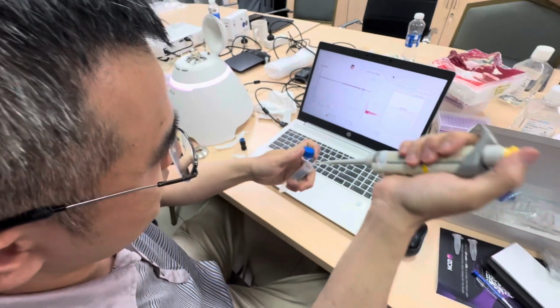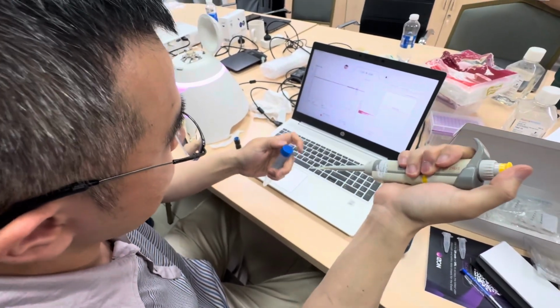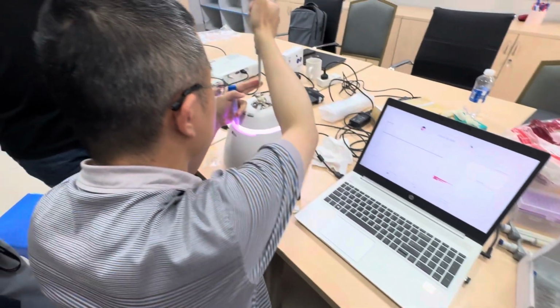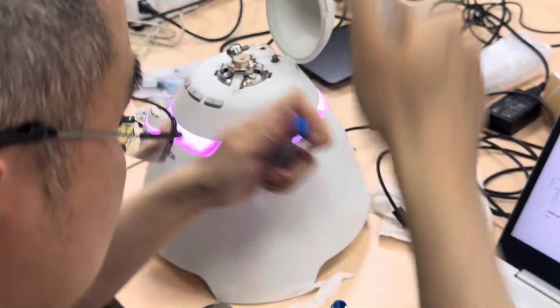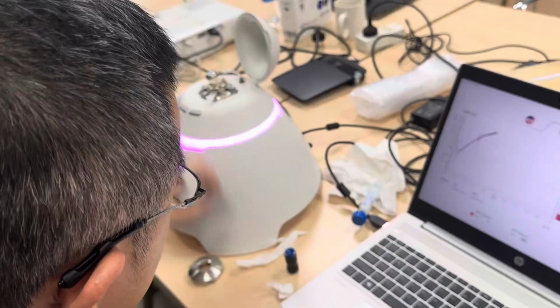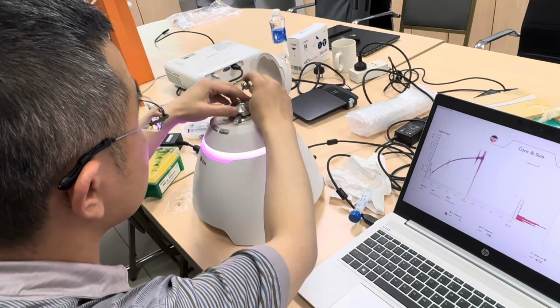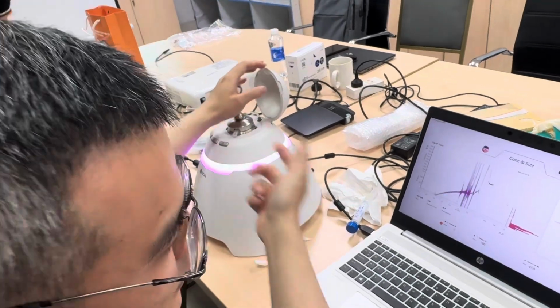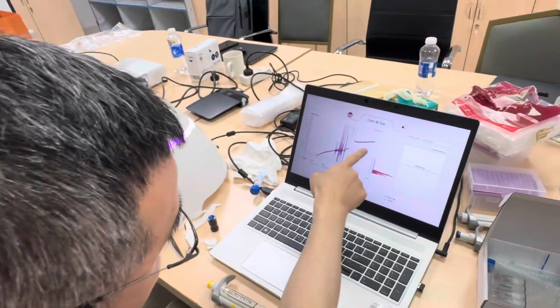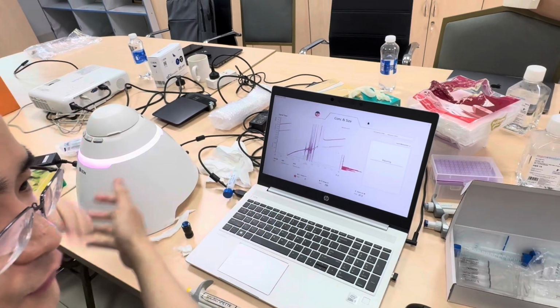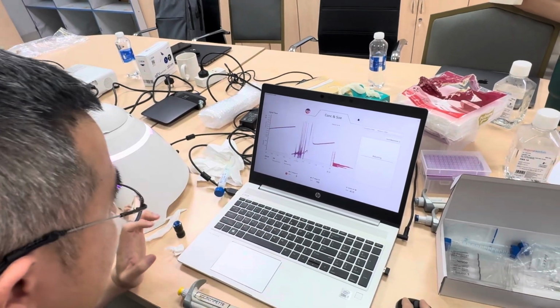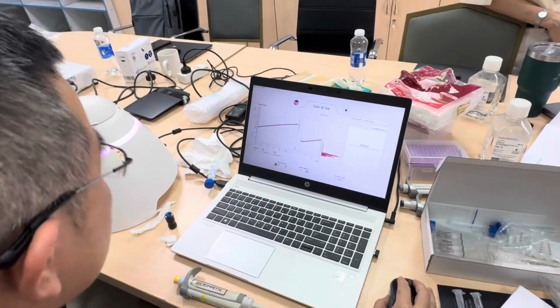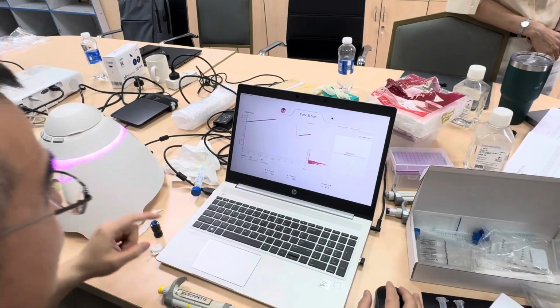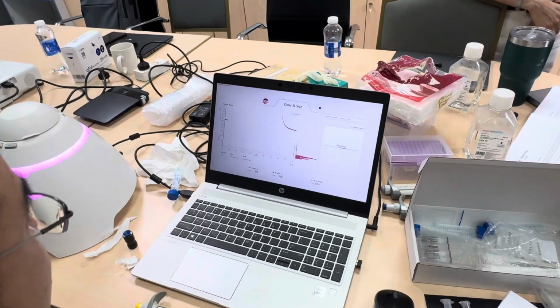Fresh running buffer, because we need to check there is no particles in it. If there is particle in it, it will affect your sample reading, which means your sample contains the previous calibration particle. Yeah. Here you see there's no particles, which means the clean just now is very sufficient. Because I accidentally unplugged the pressure nozzle, it returned an error. But now you see here.